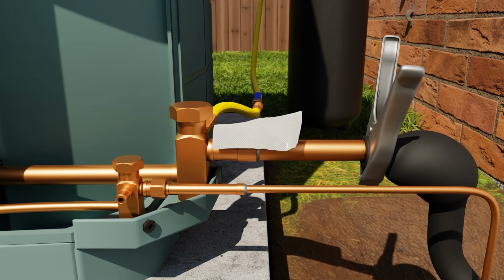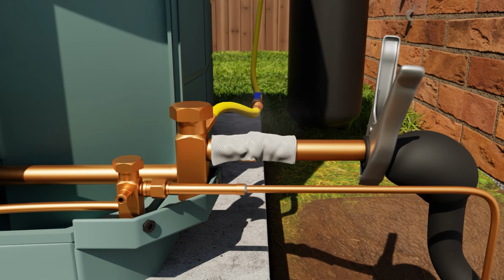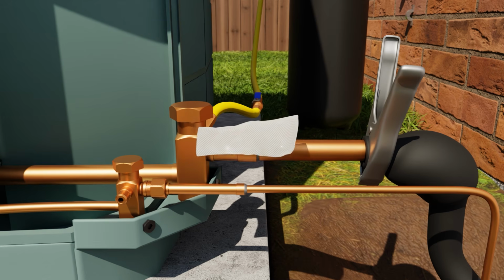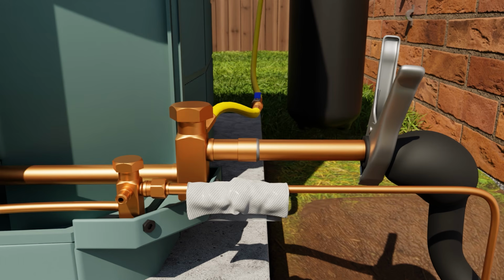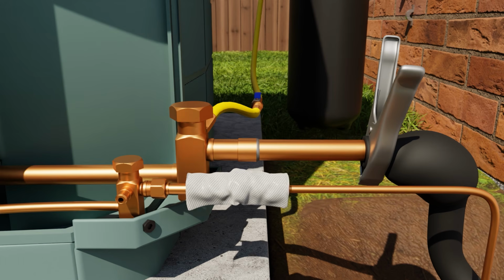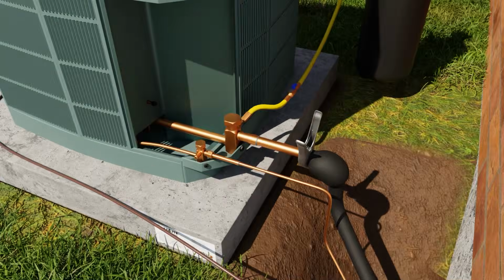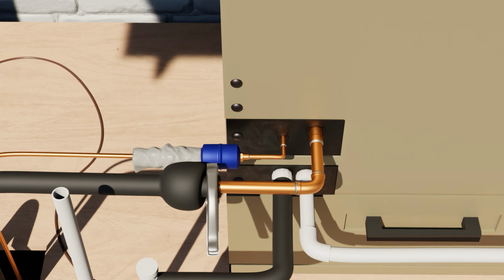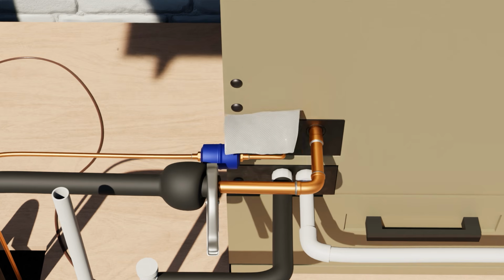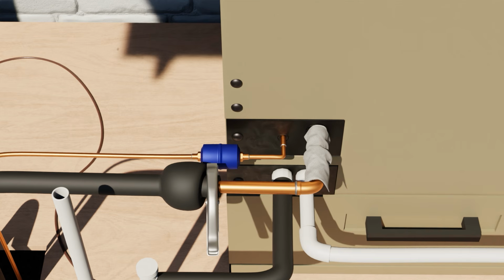If you find that Refrigeration Technologies wet rag has become hard or difficult to deal with, you can put a few drops of water in it once you return it to the container. Now you go through the system with your damp towel, cool off everything, and clean off each connection. Again, you don't want to do that instantaneously after you finish the braze, but about 20 seconds or so afterwards gives it enough time to set up and cool down so that you can cool it without stressing the connection.